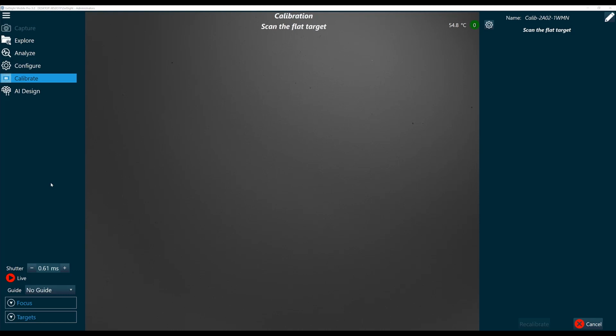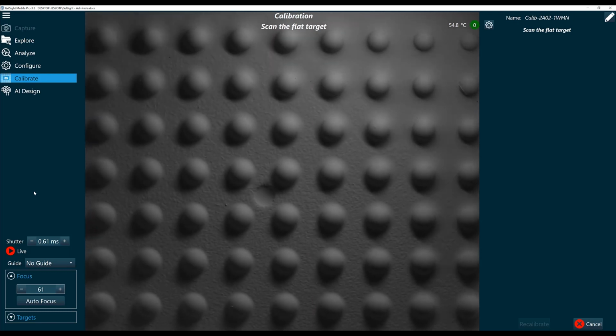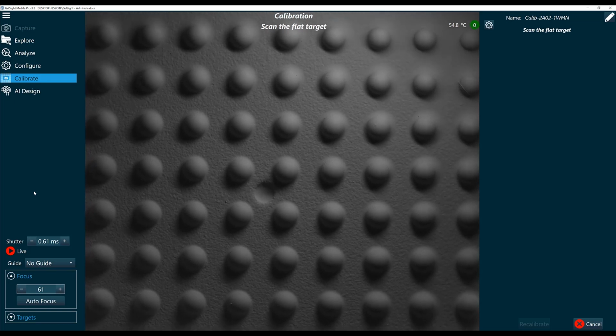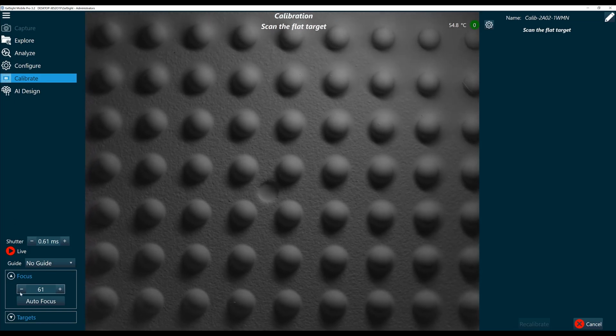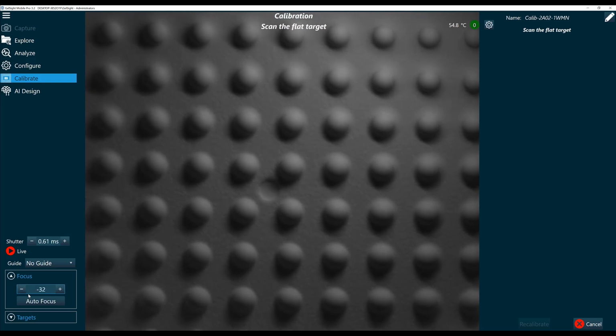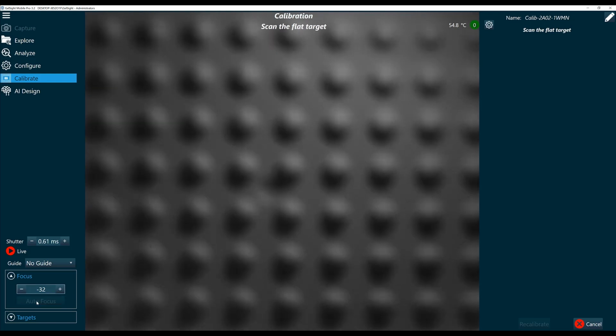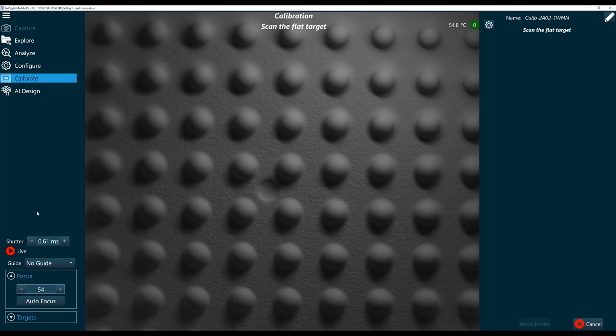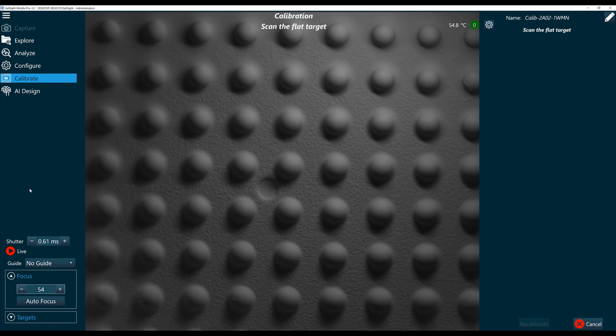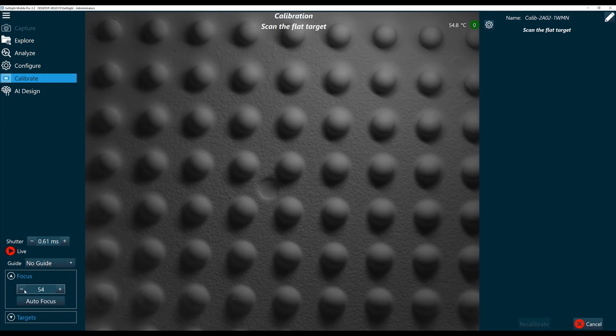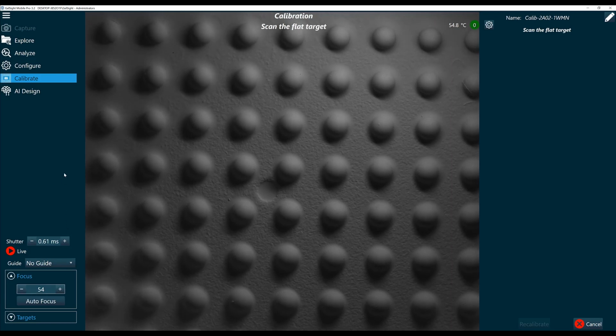Next, we're going to focus the system. Autofocus ran automatically when I entered calibrate mode, but we can verify the focus by looking at our ball grid array. This image looks in focus, but let's say it looked out of focus. If your image looks out of focus, go ahead and click the autofocus button. It will run through a focus routine and set the focus of your system. You can also manually control the focus with the minus and the plus signs.